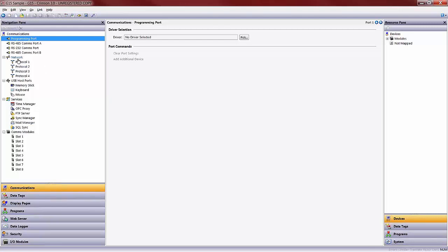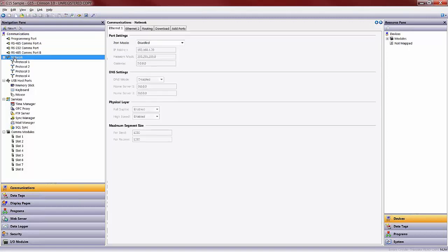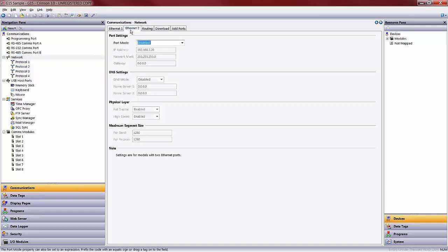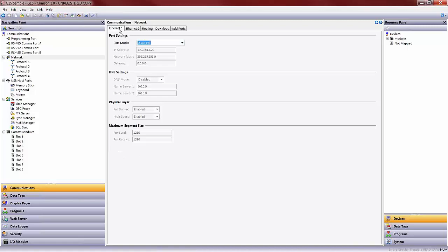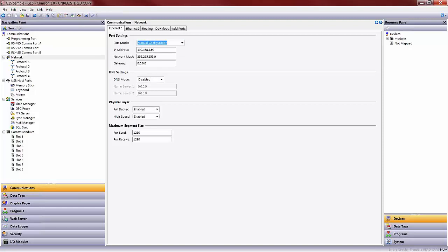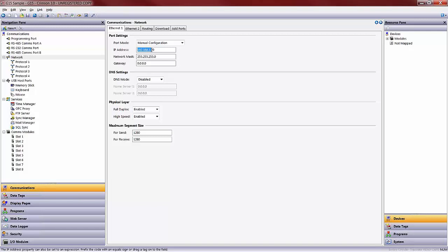We are going to start in the communications section to connect and communicate to a GE IP controller. The first thing we need to do is to set the IP address for the Red Lion device, in this case the G15. In order to do that we will want to click on Networks. The Networks section allows me to set either one or up to two Ethernet ports, depending on whether my model has two Ethernet ports built in, or I have added a communication additional Ethernet port. You can have up to two Ethernet ports on any device. In this case I am working with one Ethernet port, so I will click on Ethernet 1, and I will want to manually configure this to be on the same network as my GE IP controller. As previously stated, my GE IP controller and Red Lion device will all be on the 192.168.1 network.